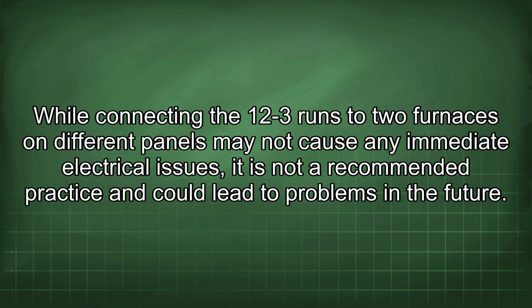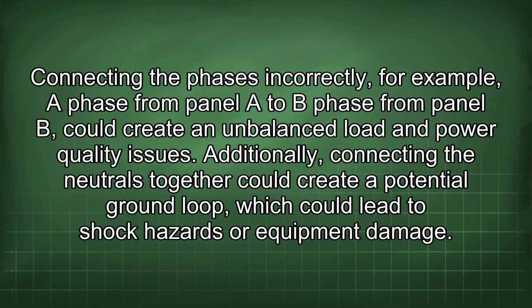While connecting the 12-3 runs to two furnaces on different panels may not cause any immediate electrical issues, it is not a recommended practice and could lead to problems in the future. Connecting the phases incorrectly, for example, A phase from panel A to B phase from panel B, could create an unbalanced load and power quality issues. Additionally, connecting the neutrals together could create a potential ground loop, which could lead to shock hazards or equipment damage.